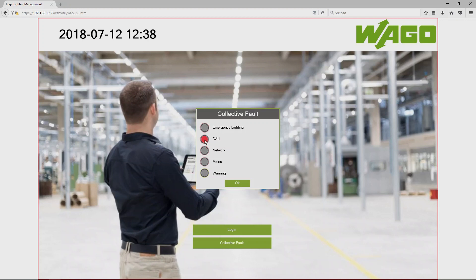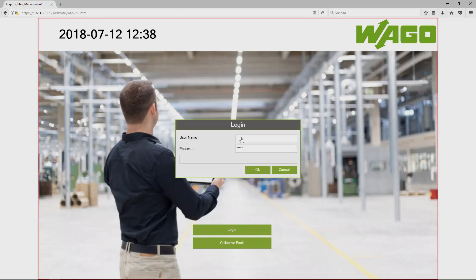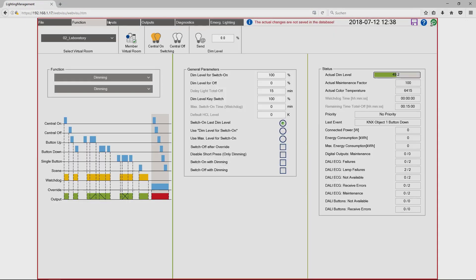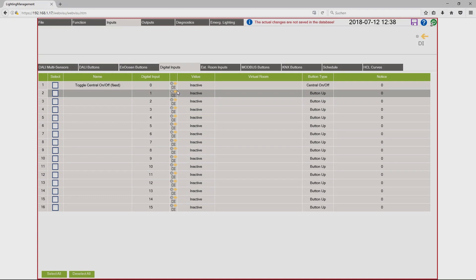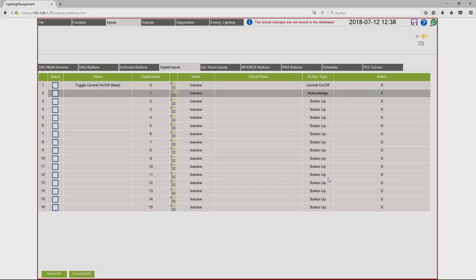To acknowledge this failure I can use a digital input. Therefore I have to log in again, admin, WAGO, go to inputs, and here you can use a digital input to acknowledge the failure. Button type acknowledge. And when the failure is gone, the lamp will be switched off automatically.